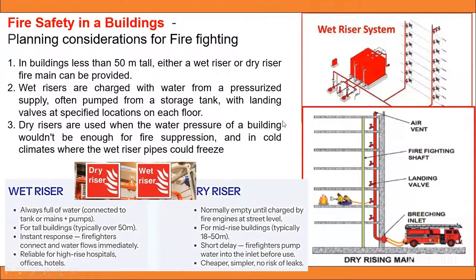Planning consideration in firefighting: we must go for various vertical protection systems, where the wet riser system and the dry riser system are there. The wet riser system is fully 24/7, the water is accumulated in all the pipelines. Where the height is more than 50 meters, we should take extra care that water is present in the pipeline. Otherwise, in a dry riser system, we have to call upon vehicles, water tankers, or the pumping system, where time would be taken. We cannot afford that time over there. So we should go for these two kinds of systems thoughtfully in an area.